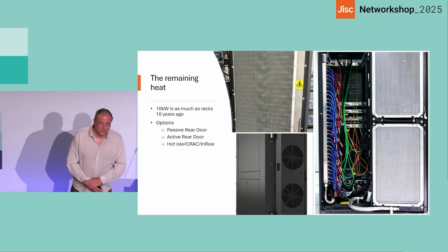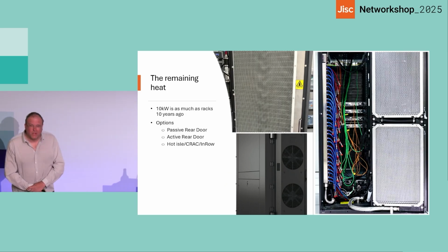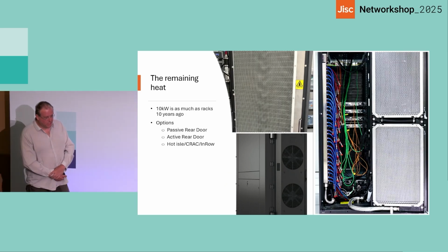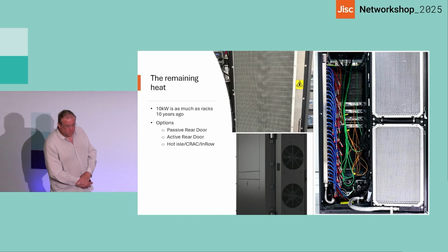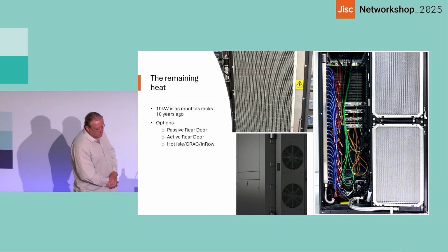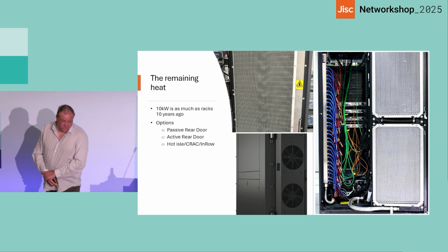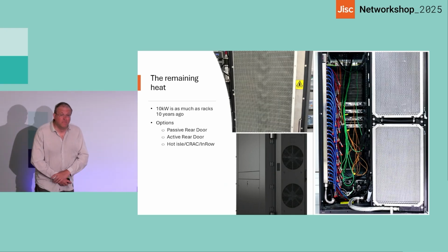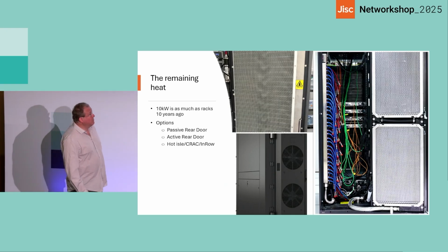As I said, you could be talking 100 kilowatts a rack. Well, 10 kilowatts used to be a rack amount of power you had. Now, 20% of 100 kilowatts is 20 kilowatts. As you heard from Daniel earlier, that's his total rack output, and that's just the excess coming off this equipment. So you could have a significant amount of heat still being generated into your room. So you're going to look at some other solutions. We've got things like passive rear doors, good for about 10 kilowatts or so. After that, we'll probably need to upgrade to active rear doors, because you'll need to pull more airflow through them to get better efficiency after the cooling. Or you can go, like Daniel had, with the traditional hot aisle, cold aisle, in-rack coolers, etc. You will just generate some heat, and you'll have to get rid of it in the traditional ways.